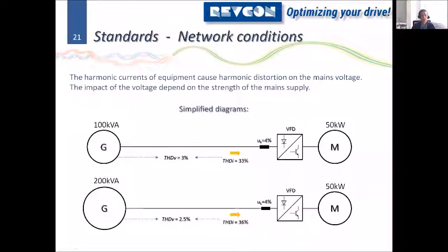So first of all, we need to understand what is the background, or what is the effect that we have when we put a drive on the main supply. So in this simplified example, we have one drive connected to two different generators. The first one is 100 kVA and the second one is 200 kVA. So double the size and very likely double the short circuit current.